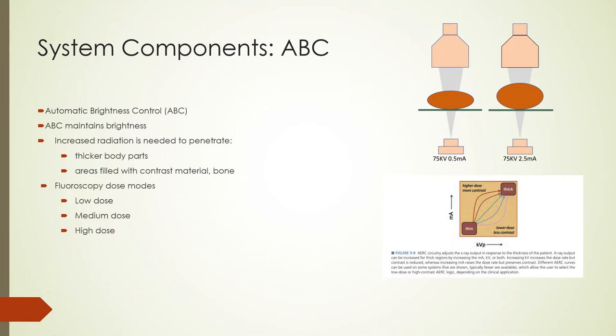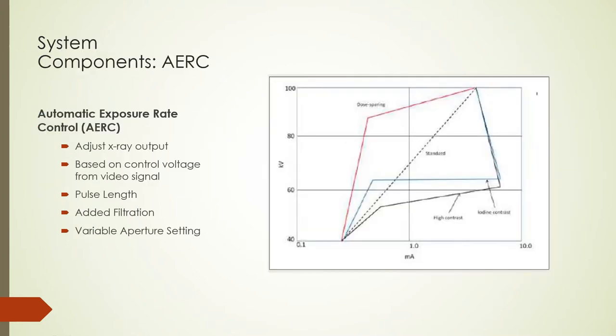Many fluoroscopy systems have several options to adjust dose and image quality, often labeled as low dose, medium dose, or high dose selections on the console — though these labels are manufacturer-specific. Automatic Exposure Rate Control or AERC is another name for ABC. AERC uses a sensor on the image intensifier input side or flat panel detector input side to maintain a constant input dose rate despite thickness or density variations. More advanced systems use a control voltage derived from the video signal to control dose rate. Additional control parameters include pulse length, added filtration, and variable aperture settings.